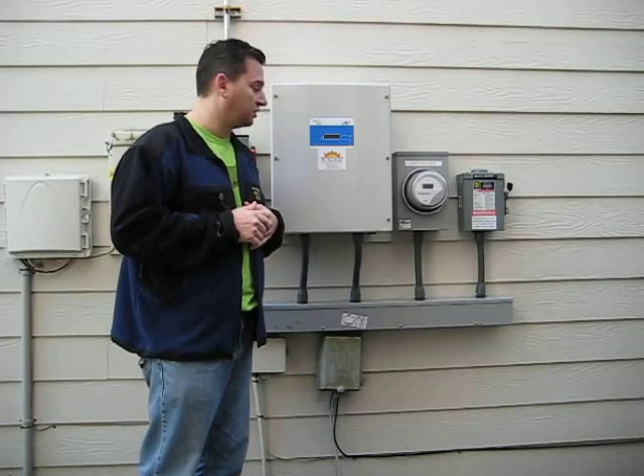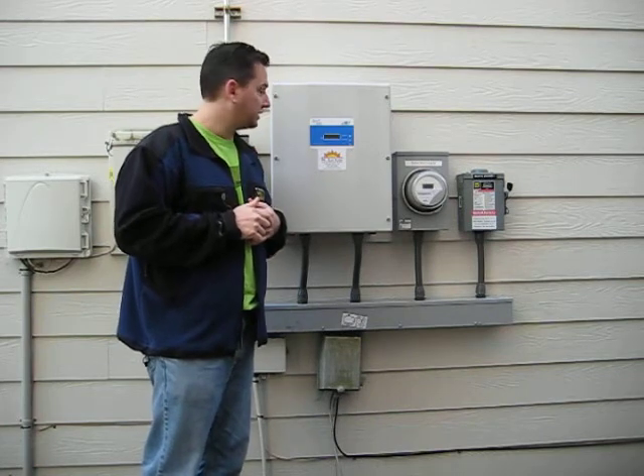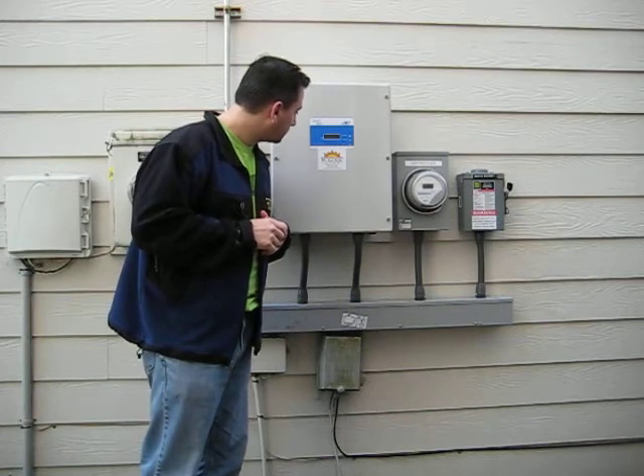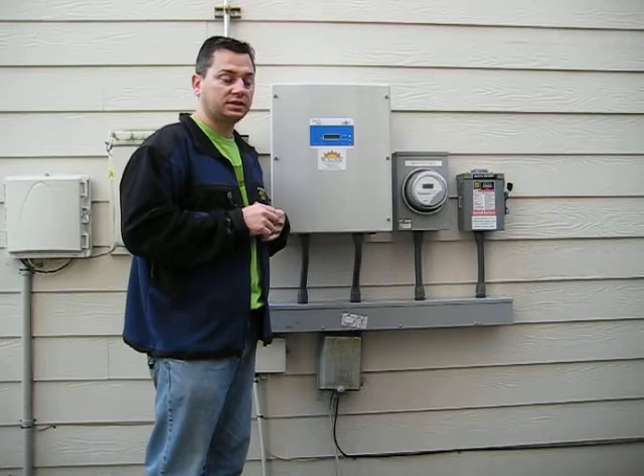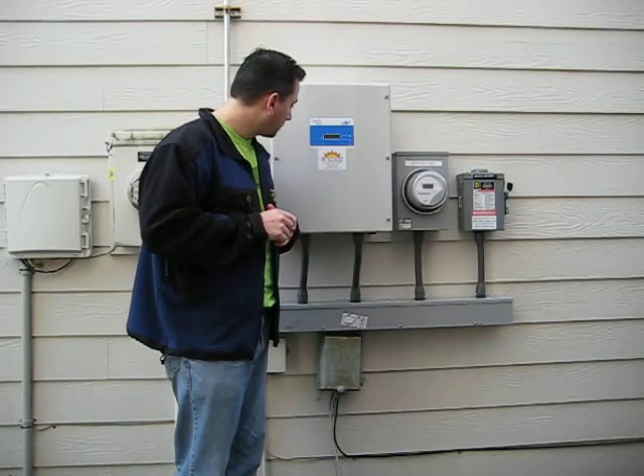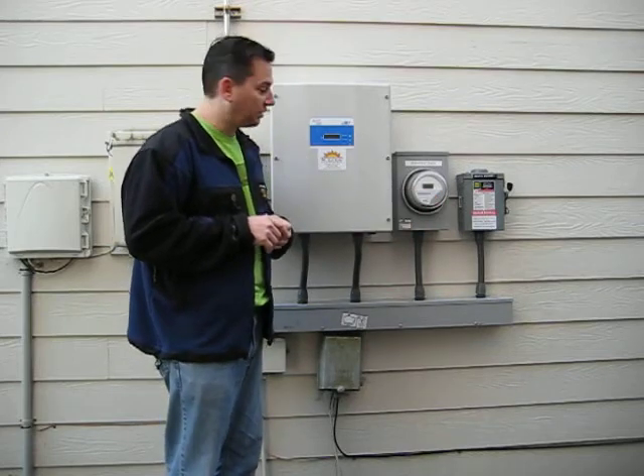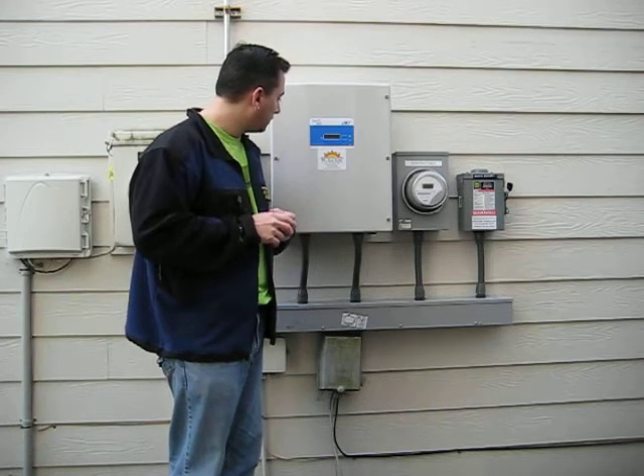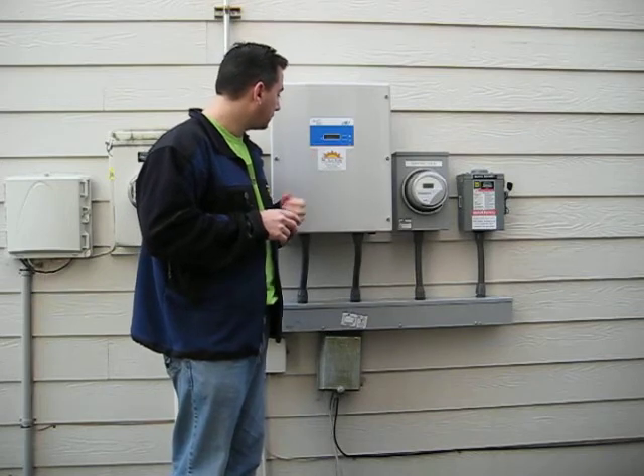It says it's generated zero watts. That makes sense. 240-volt system as expected. It's got zero volts AC. 331 volts coming in from the PV system already — that's great. Zero kilowatt hours, and we have another AC production meter that also says zero. There's at least two of the strings, so panels are reading voltage in.